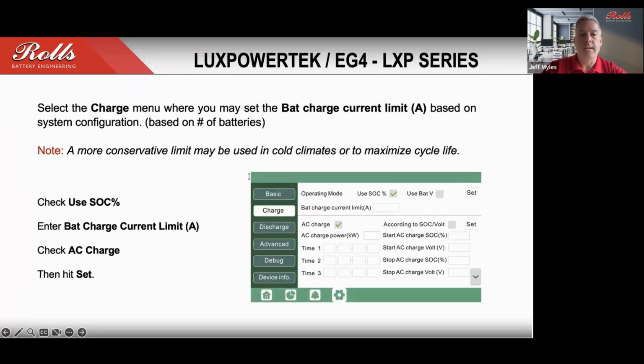So you're going to set up things like the state of charge, and the battery current limit is going to be set as well. It's important that you set that so that you're not exceeding the limit on the stack based on the particular number of modules that you're assembling. And then for any of the other settings outside of charge and discharge on the battery, offered within the inverter, you would need to refer to the inverter manual. So we've essentially just covered the basics as far as communication, charge and discharge, and any required settings.